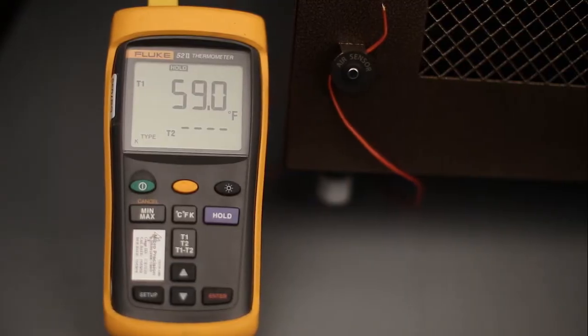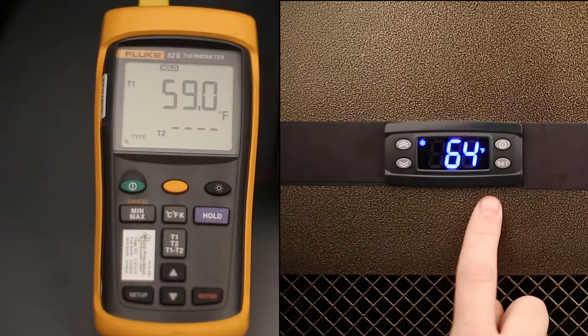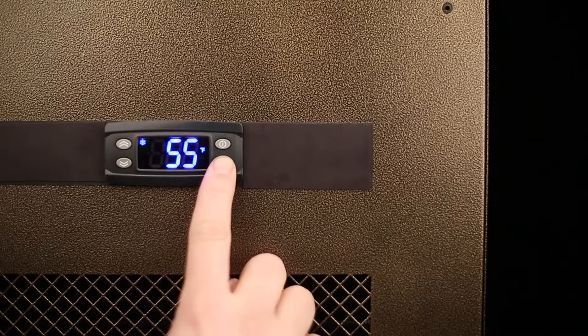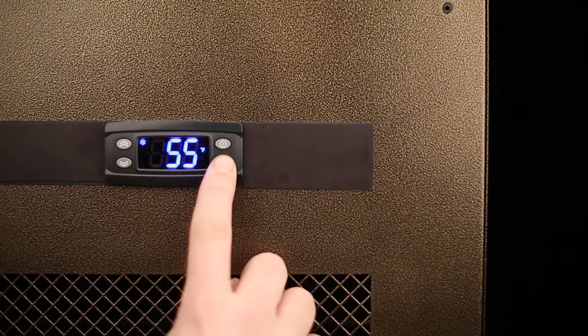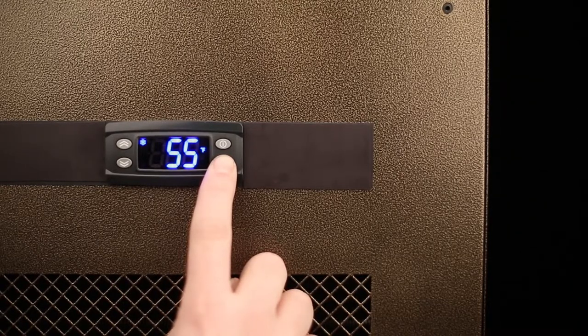View the temperature of your external thermometer. In order for these two temperatures to read the same, the temperature probe needs to be calibrated. To perform this function, press and hold the set button for five to seven seconds. This will bring you into the hidden menu.